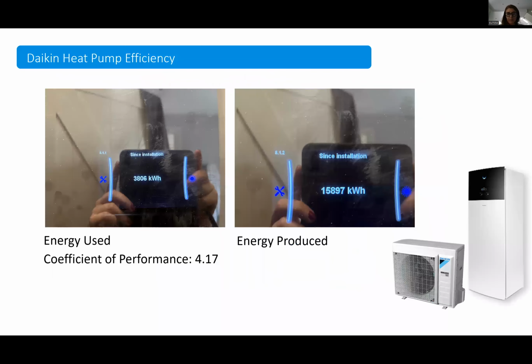And to give you a real life example, this is my own heat pump that I have in my own house. It shows you the energy used and the energy produced. You can see this heat pump has been in for about a year. It used 3,806 kilowatt hours of energy, and it produced 15,897 kilowatt hours. So this has given me a coefficient of performance of 4.17, and that's across both heating and hot water. So I'm pretty happy with that. So that's basically it. That's the overview. I hope it's been useful. And if you have any questions, please feel free to go ahead and ask.